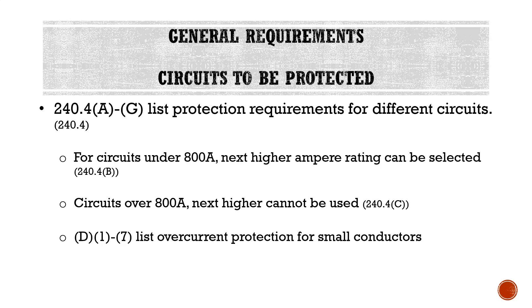Section 240.4 D1 through 7 covers overcurrent protection for small conductors. This section tells you that for 18-gauge, 16-gauge, 14-gauge tap wire and so on, you can only have a maximum size overcurrent protective device of a certain size.